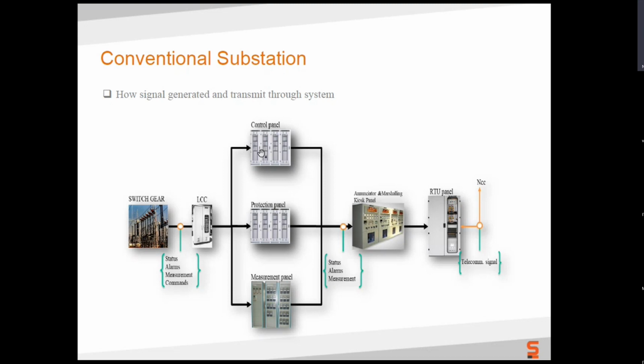And then we have separate control panels - you have many panels in a relay room if you go to an old substation, like we have one old substation in power grid that is very old but has now become automated. At another plant's switchyard, they have not moved to SAS yet, so they have many panels - control panel separate, protection panel separate, measurement panels separate. It's a very strange kind of thing nowadays.